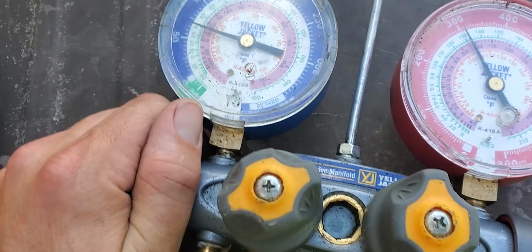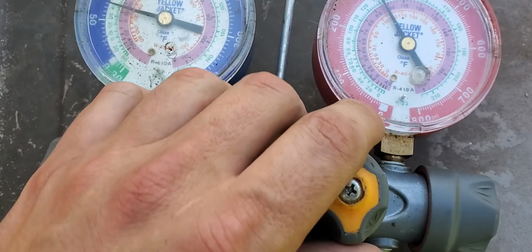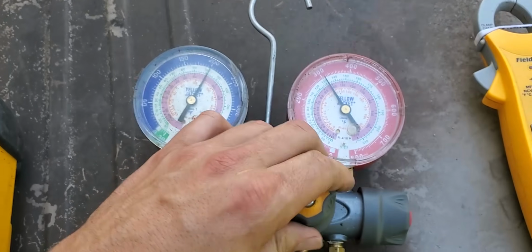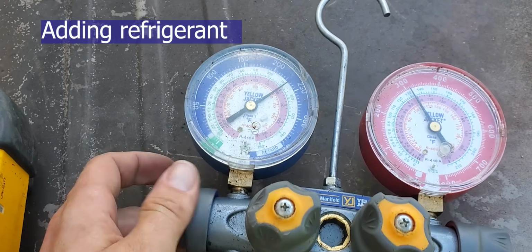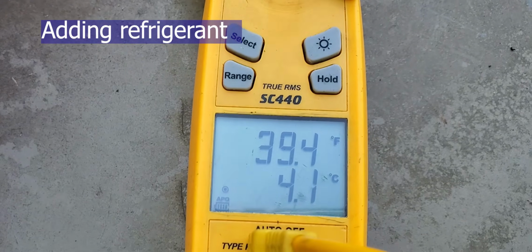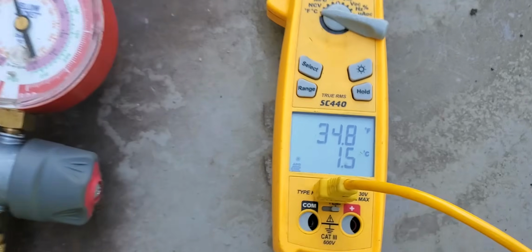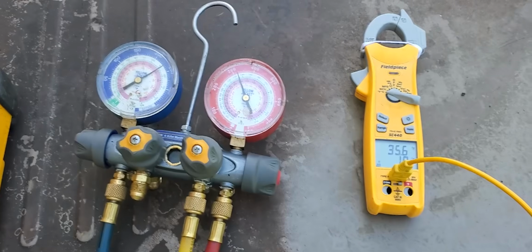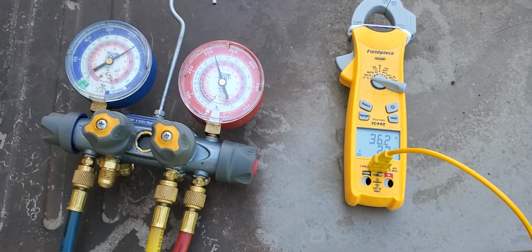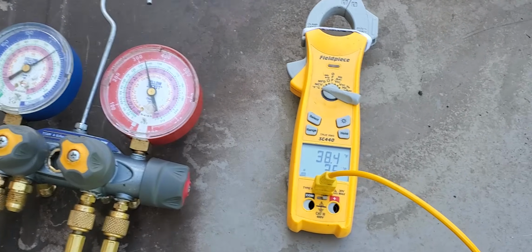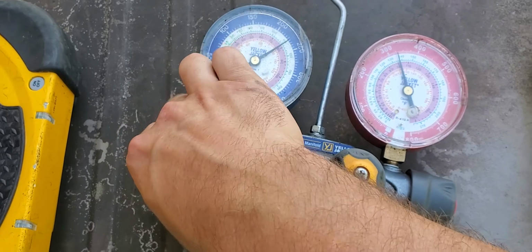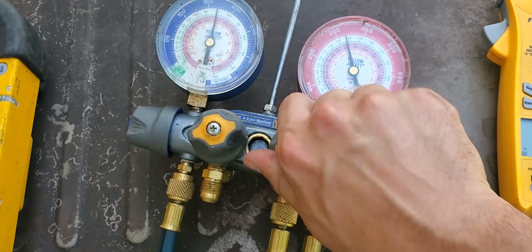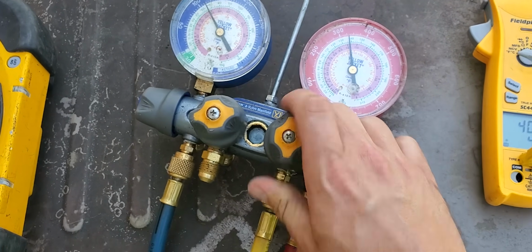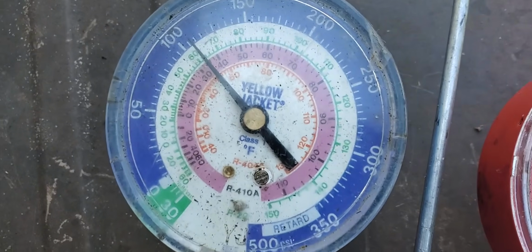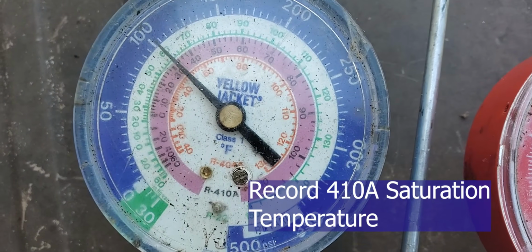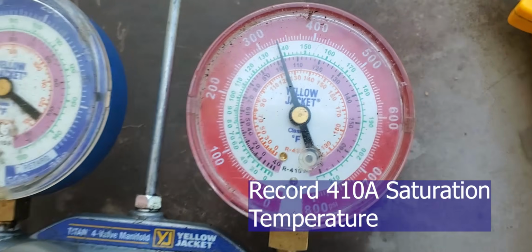The subcooling method is generally used to check charge in systems with a thermostatic expansion valve, or a TXV. The superheat method is used to check charge in systems with fixed orifice metering devices, such as capillary tubes. These two methods can be used to check refrigerant charge as part of the troubleshooting process, or after system charging, to ensure that the proper quantity of refrigerant has been added to the system. Let's go into what we need.